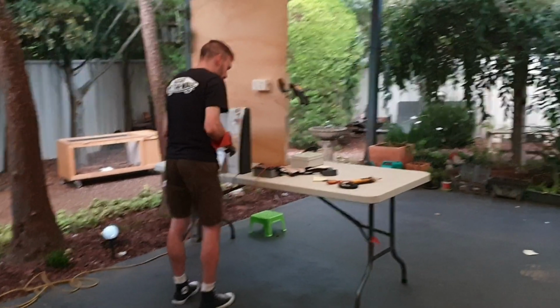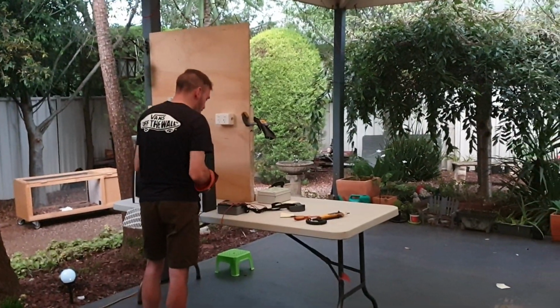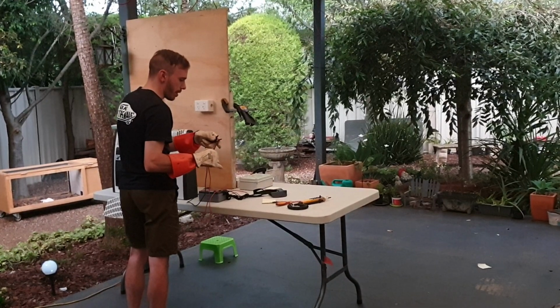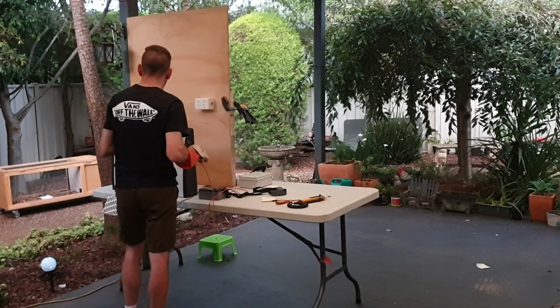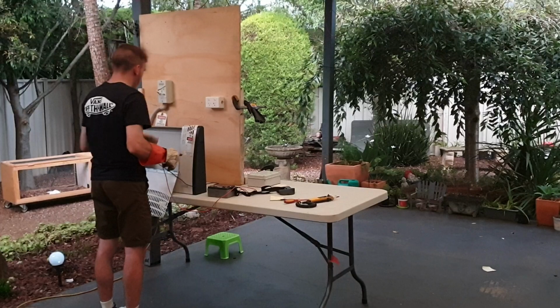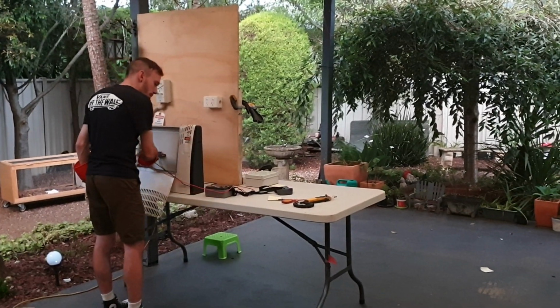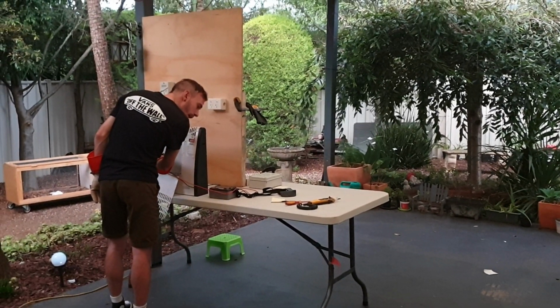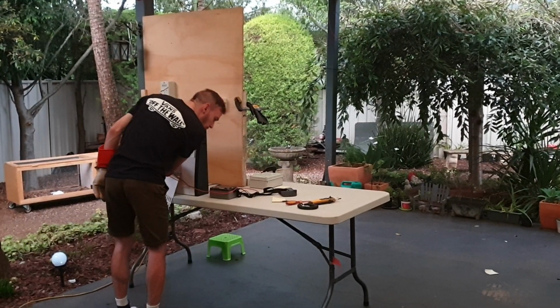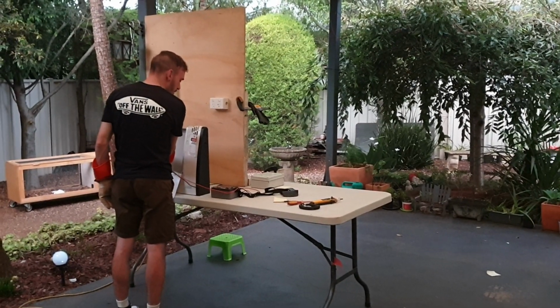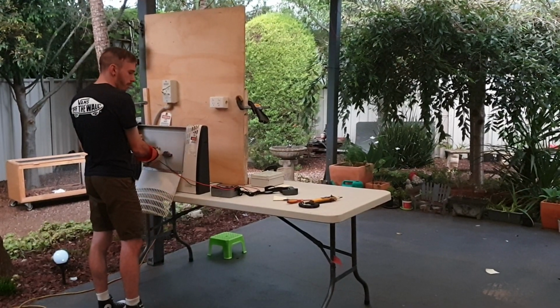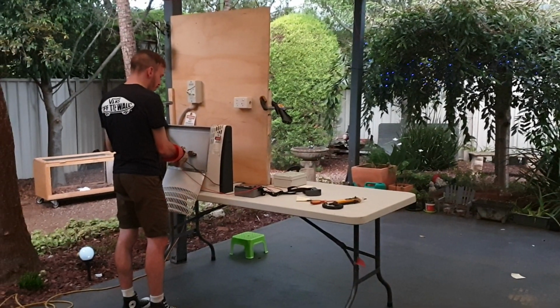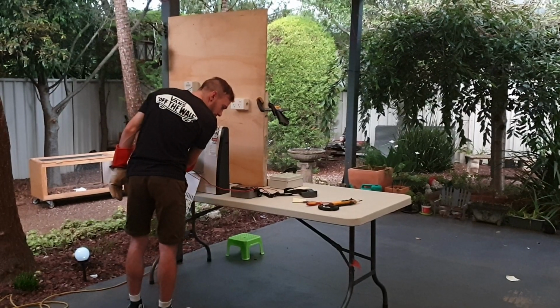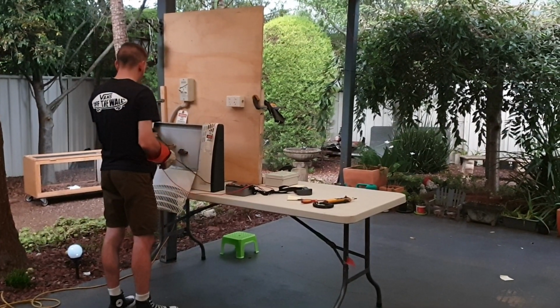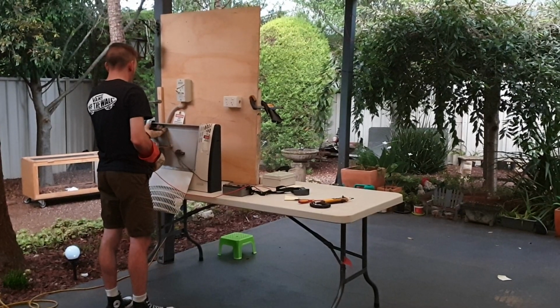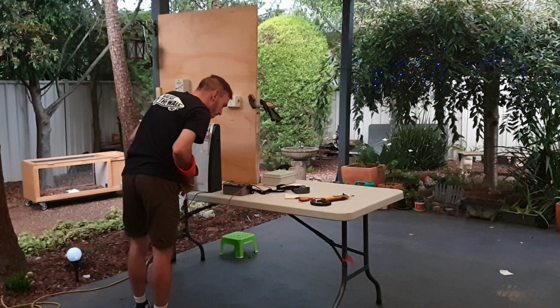Yep, that's fine. And the next test we're going to perform is on the 500 volt 200 mega ohm scale. We're going to zero the meter again. That's fine. Now I'm going to put it from the frame to the active terminal, and that is 1.5 mega ohms, which is a pass. It has to exceed 1 mega ohm. Now we're going to go from the appliance frame to the neutral, which is infinite mega ohms, which is a pass. I'm going to test the meter one more time.